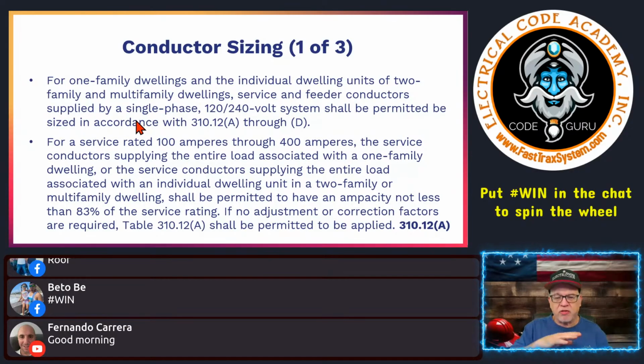So you're allowed to use this 83%. This is for the conductor sizing, right? So it's a minimum size for the conductors. And you also saw yesterday that we had an allowance when it came to the overcurrent protection in 230.90 to be able to use the 83% and still consider it protected from overload. That wasn't a problem, even though it may be smaller conductors than the breaker they're terminating into. We saw that yesterday, so make sure you go back and watch that part if it's confusing.